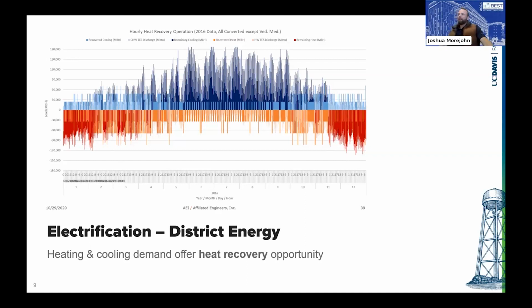And so if you can do that, then suddenly your heating load, shown in the red here on the bottom, over the course of a calendar year, you can see the heating of course higher on the negative y-axis in the winter months, but a majority of that heating load, shown in orange here, is what can be met from the heat recovered from the cooling load. So if you have heat recovery chillers, that light blue on the top of the y-axis, that cooling can be captured and provide the heating load that's on the orange on the bottom side of the axis. So we're able to do about 50 to 60% of our heating load just with heat recovered from our cooling system, meaning that's the reduction in our gas demand with this heat recovery chiller plant and hot water instead of steam. So that's the goal.